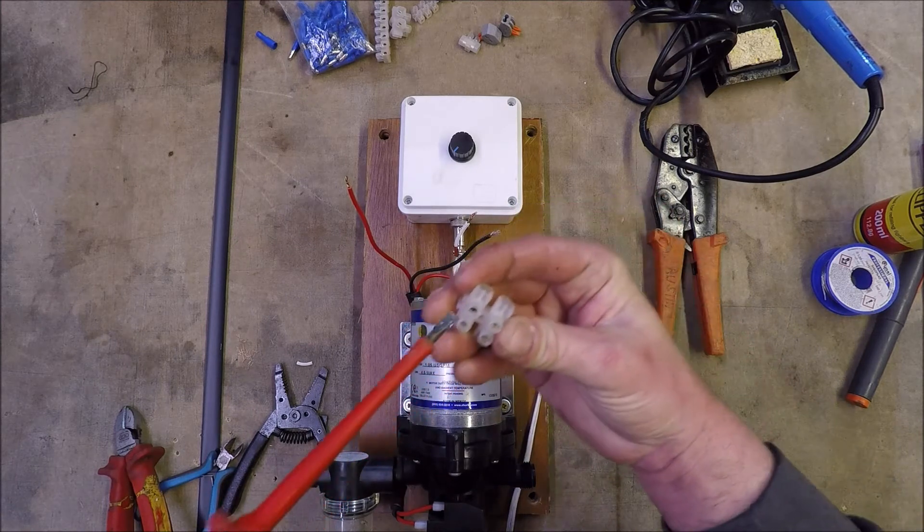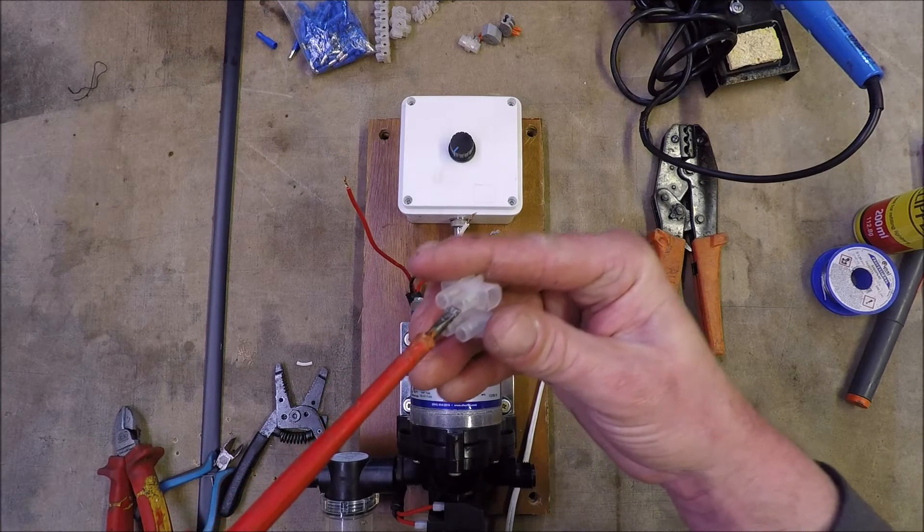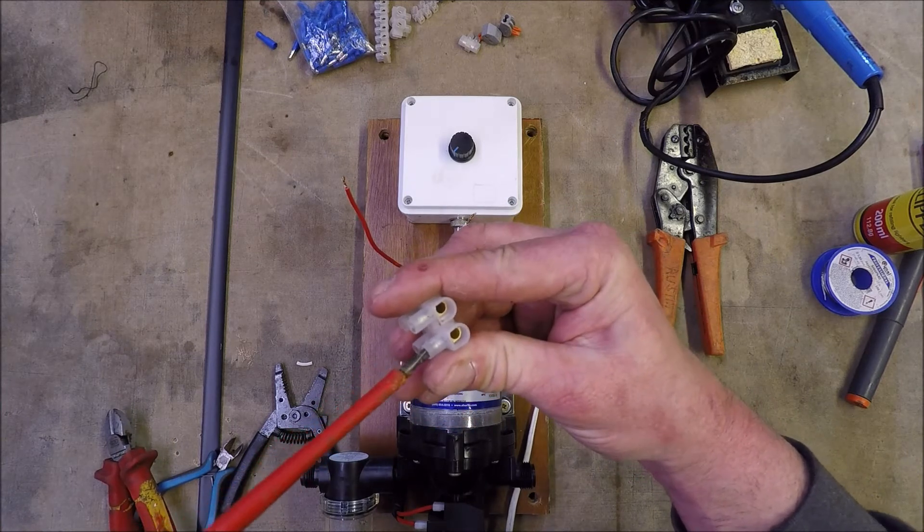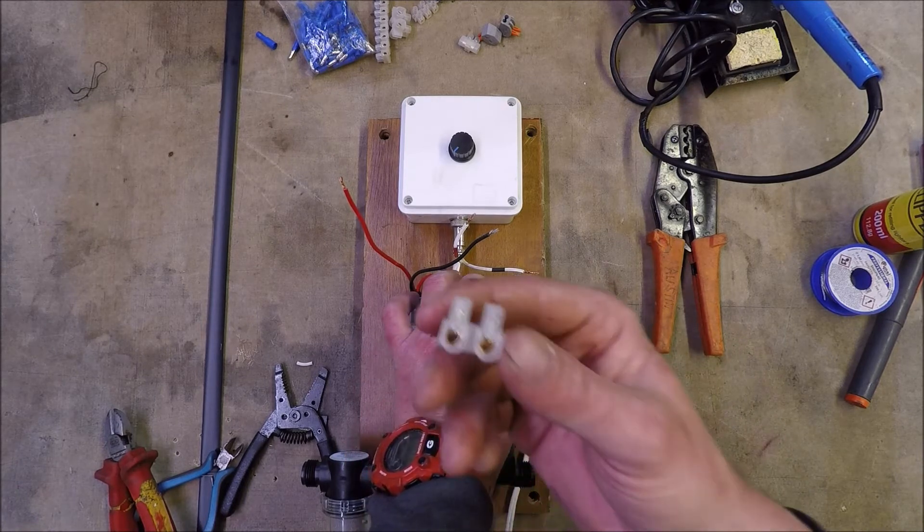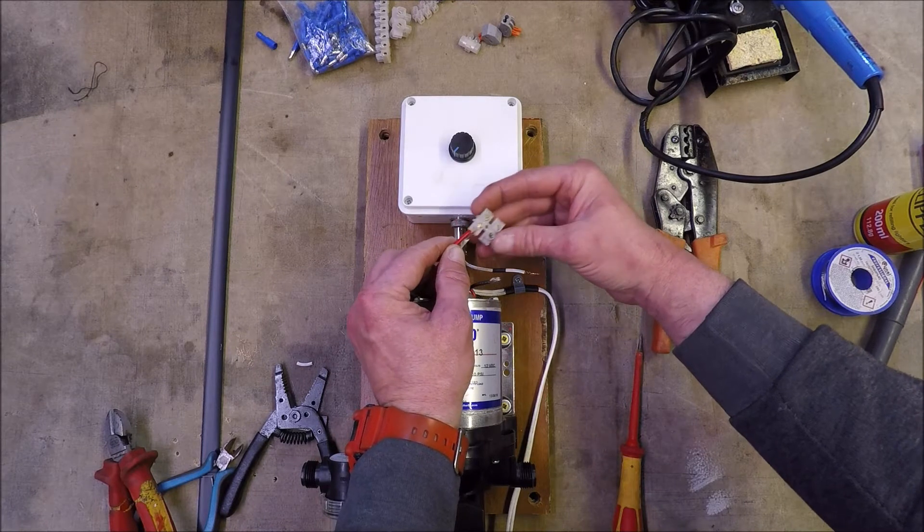If you have these and keep them as spares in your van, always with a screwdriver screw the screws all the way in snugly so you don't lose the grub screws out of them. Do not over tighten them because you can shear the thread off or crack the brass. Wires go into this.